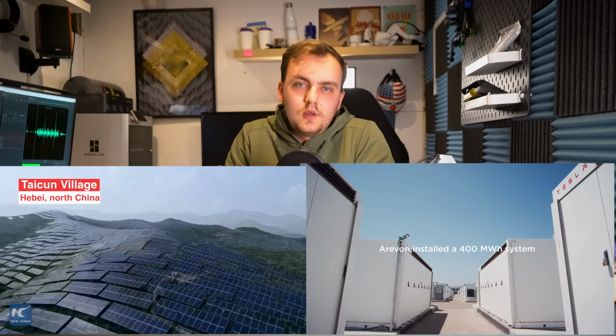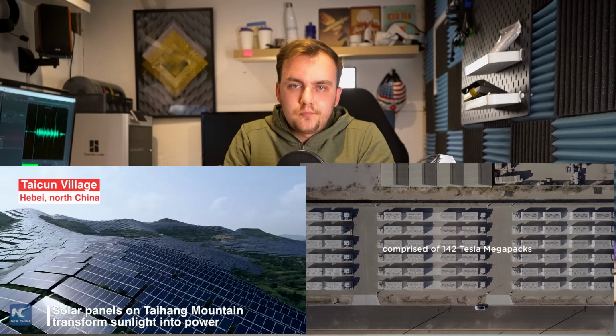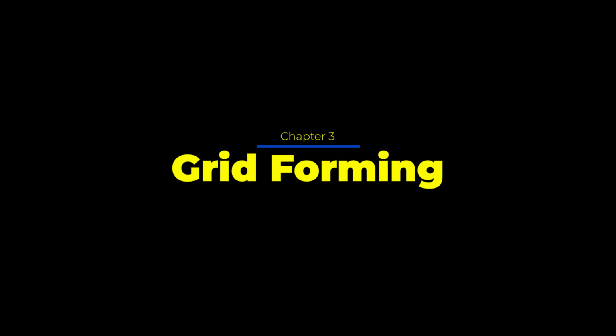Well, battery storage and solar have no moving parts, so no spin and mass to give it inertia. They produce DC power like most wind turbines do, which then needs to go through an inverter to become AC power. Some of these inverters operate in what's called grid following mode, where they need a stable grid frequency already present in order to export power. Whereas smarter inverters are what's called grid forming, which can operate in island mode, where they set their own frequency and voltage on their own like a microgrid.